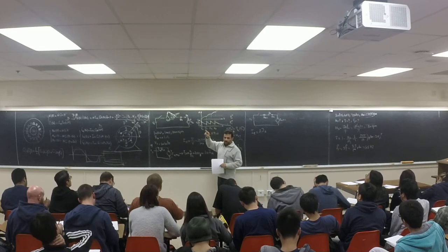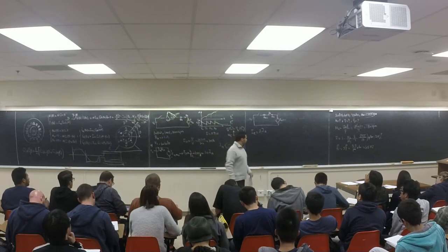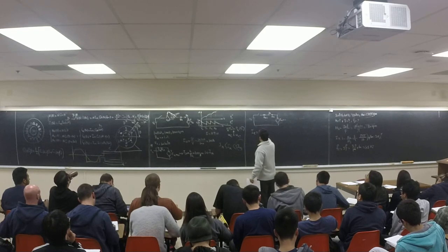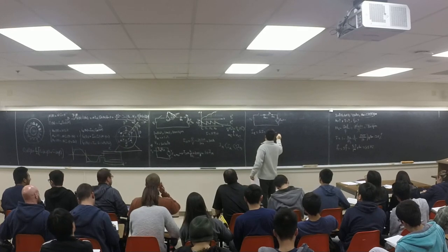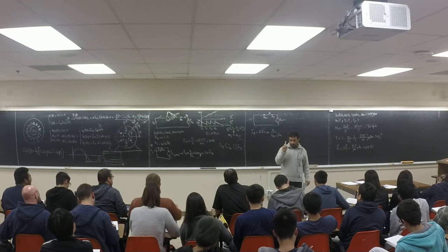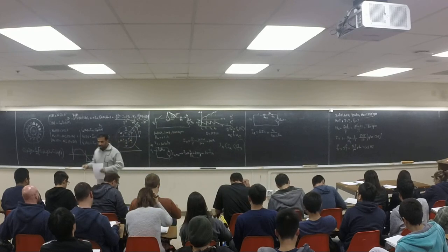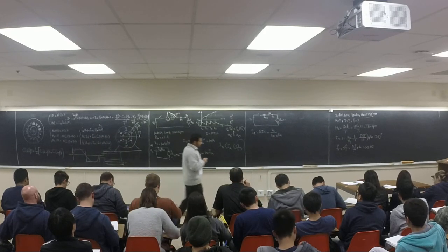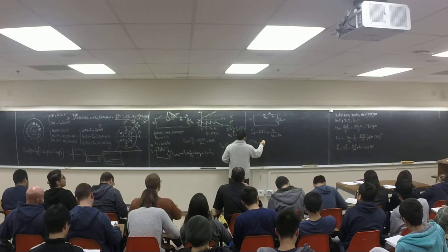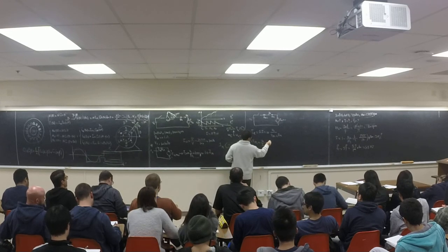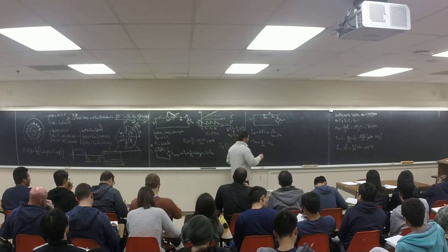So I'm going to put enough resistor to limit the current to 200 amps. I'm not going to let it go to 1000 amps. This is just for the startup. Be careful: there is no E in the startup. E is zero for the first state. So how much is the RST1? How much is the VS? 100. How much is the IA? 200.